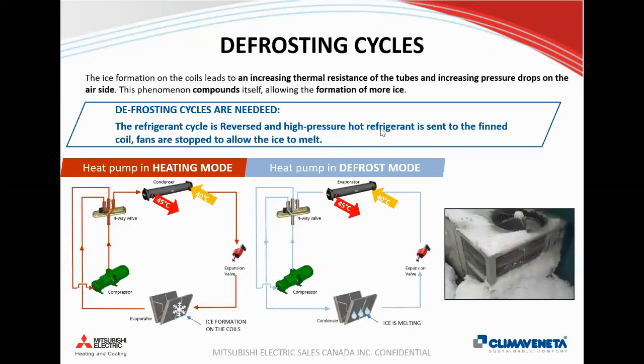The other thing with air to water heat pumps, or any type of air source heat pump really, is that defrosting cycles are required. Typically with these types of systems, this is showing the heat pump operating in heating mode, where we have a condenser providing hot water to the building, and we're doing this by running a compressor and using an evaporator coil where we're extracting heat from the environment.